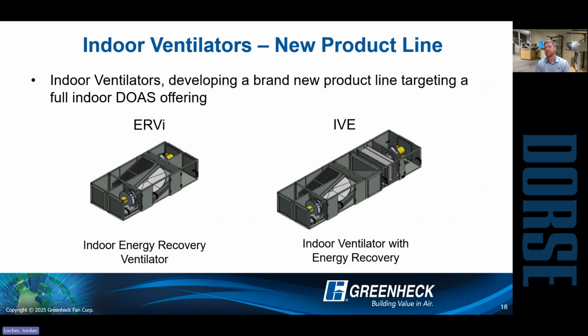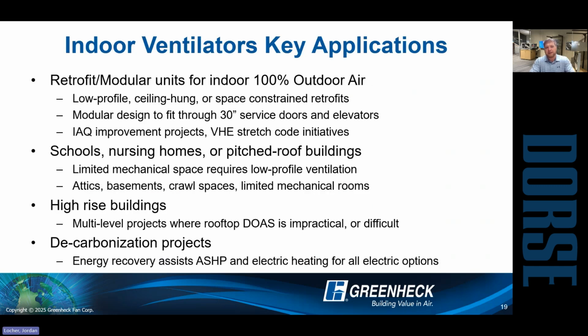Basically the difference being, ERV only, or do you want some additional post tempering, right? So depending on which part of the state you're working in, you may or may not need that. So really, why did we drive towards this? We're seeing as this technology picks up in the market, that retrofit modular need is growing. It's very high, right? So offering a low profile ceiling hung unit, typically going into some crazy space that you can't get into, and how do I get the unit in the building? So we designed a unit that was completely modular and would fit through 30-inch service doors and elevators, right?